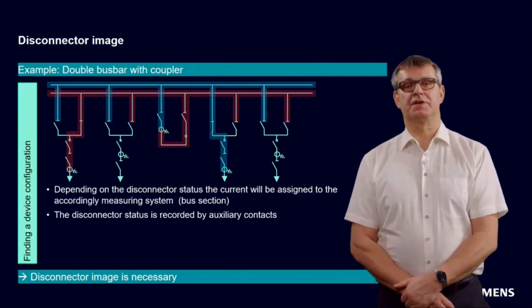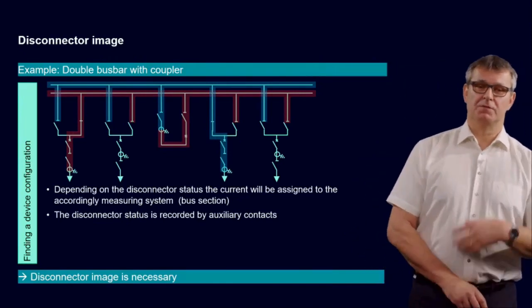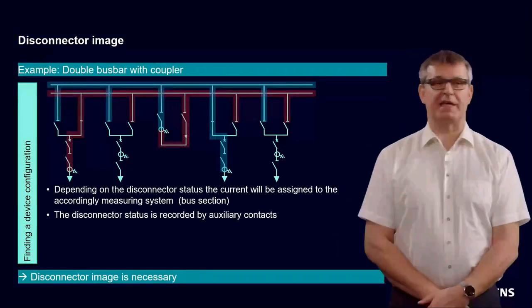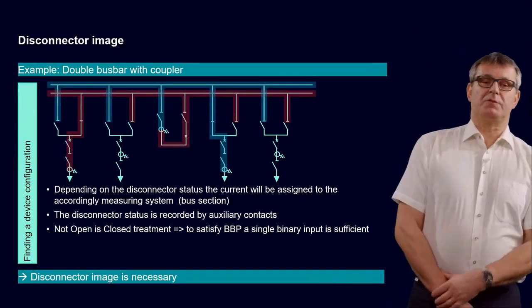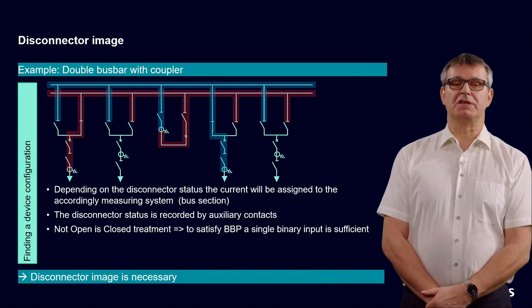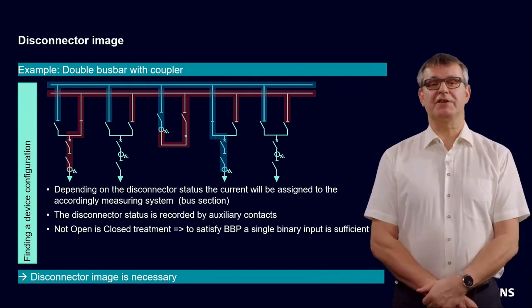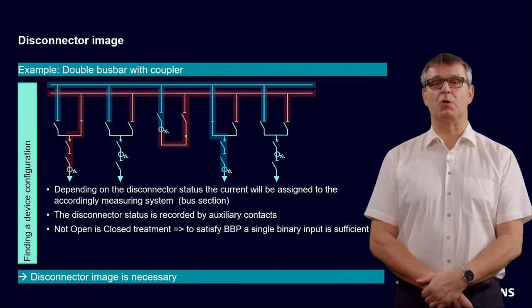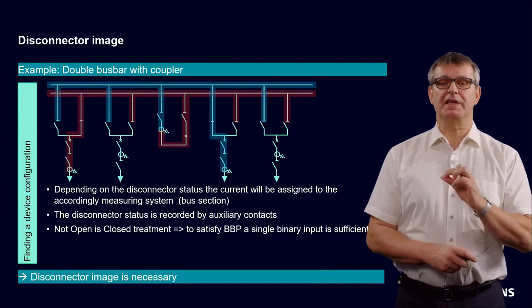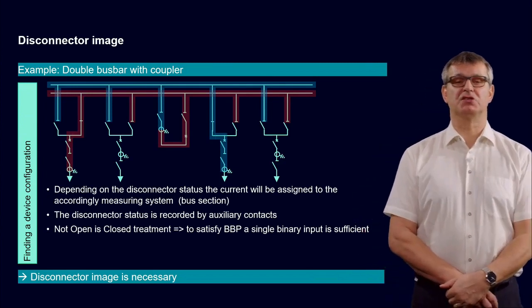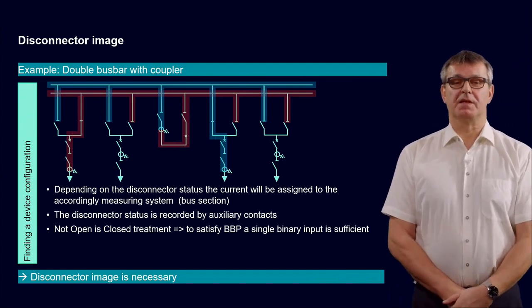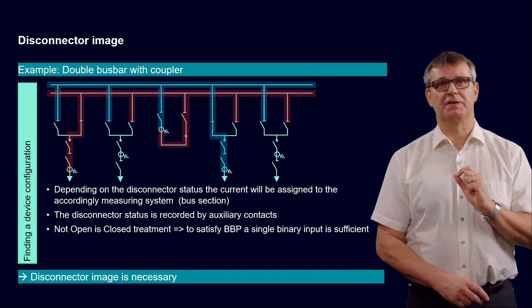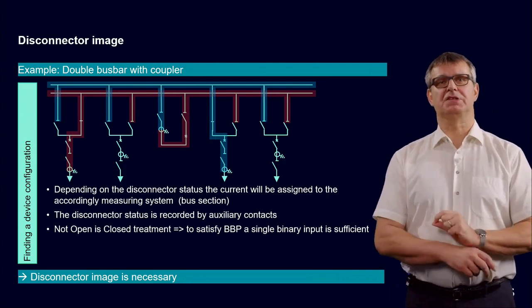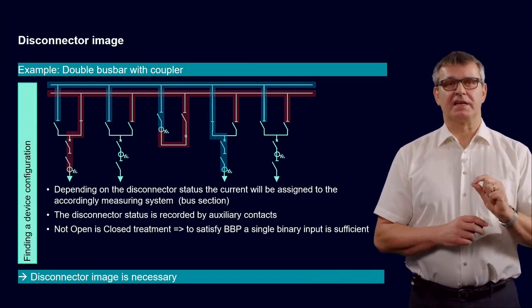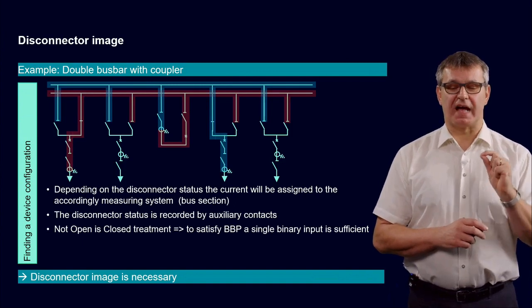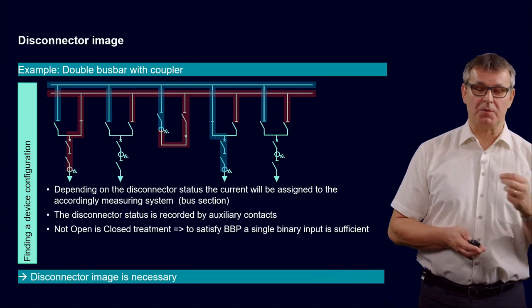The disconnector status will be recorded by auxiliary contacts. We will explain this in detail in our second tutorial. And like in the 7SS52, we have this not-open-is-closed treatment. This means that, especially in the sensorless busbar protection, where sometimes we may not have so many binary inputs, one binary input may be sufficient for this not-open-is-closed treatment. But it's very important that if we use only one binary input, we have to use a normally closed contact of the disconnectors, which gives us a clear signal with a high signal whether the disconnector is open or not.